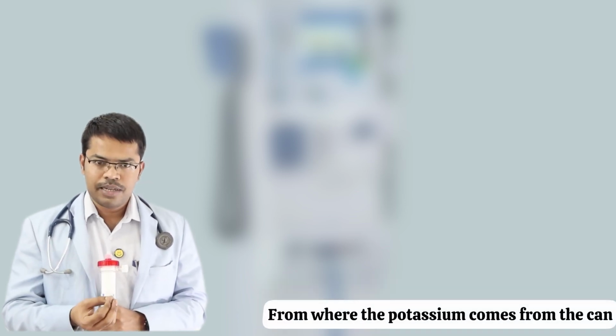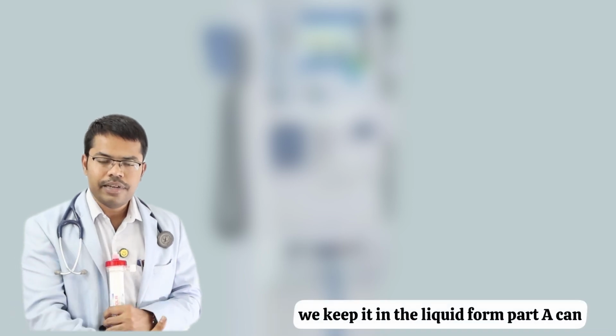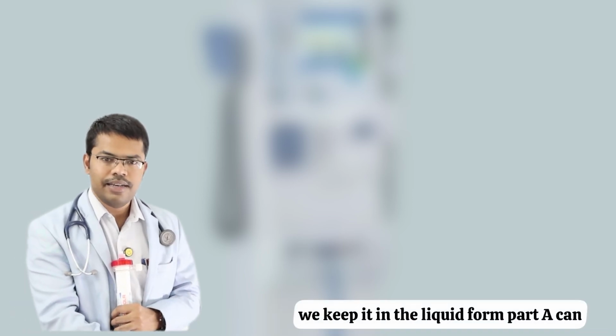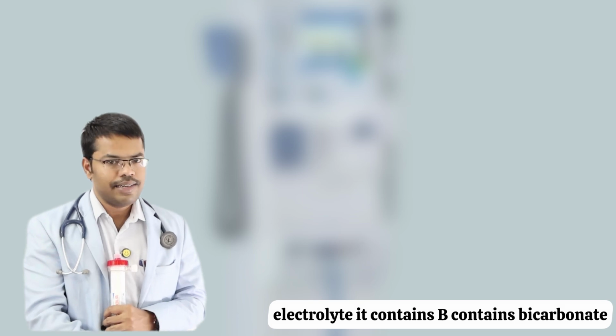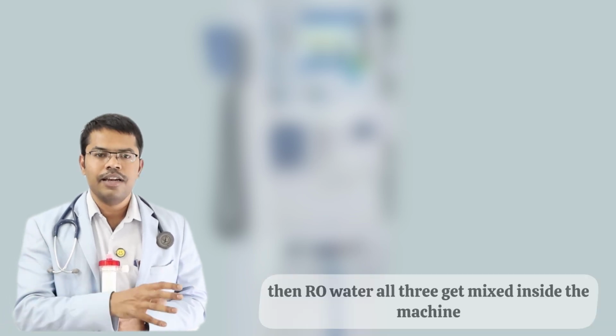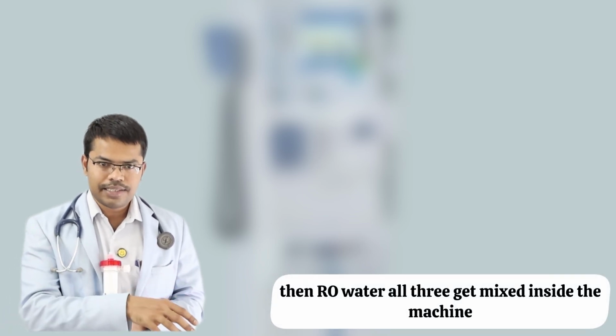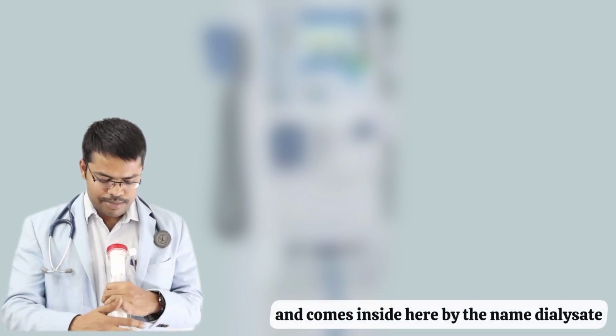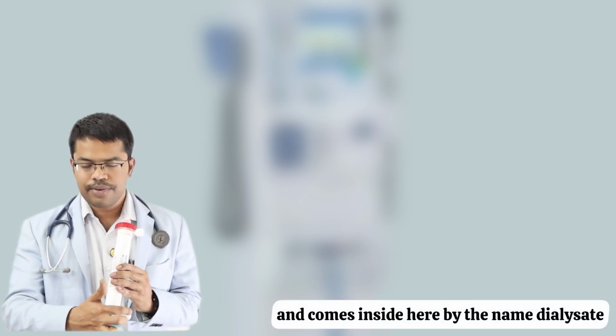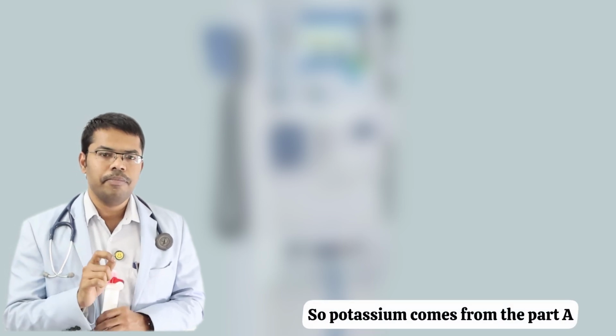From where does the potassium come? From the can. We keep it in the liquid form, part A can. It contains the electrolytes. B contains bicarbonate, then RO water. All three get mixed inside the machine and come inside here by the name dialysate. So potassium comes from the part A or the electrolyte can.